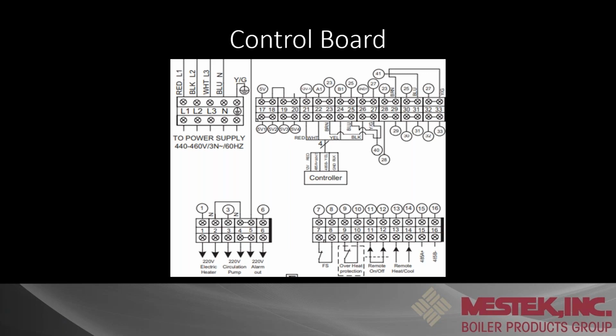So if we need to turn a light on or some type of alarm, we can do that. And then moving over to 7 and 8, that's your flow switch. So it's not going to run if the flow's not there. 9 and 10 is our overheat protection. And then 11 and 12 is your remote on-off, excuse me.